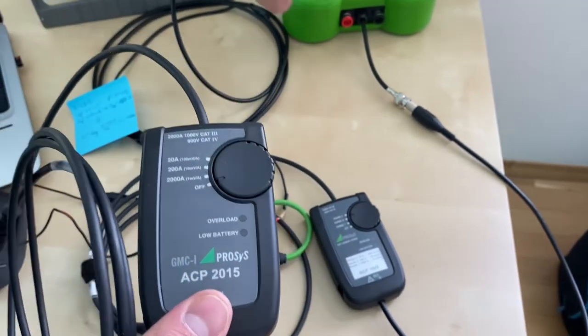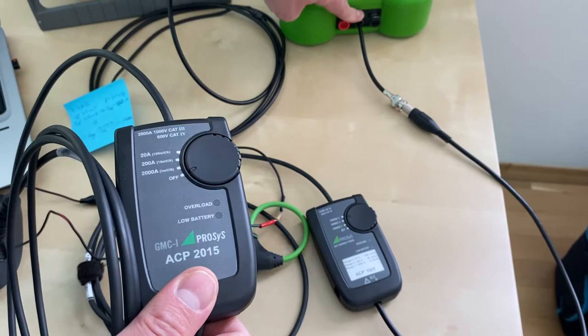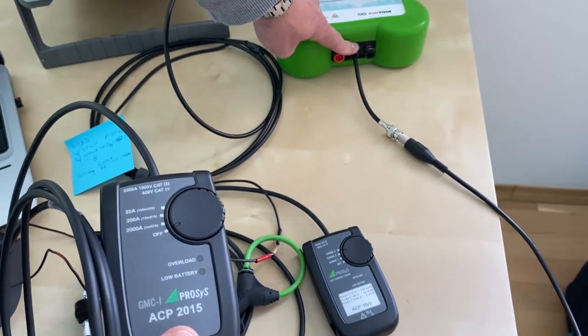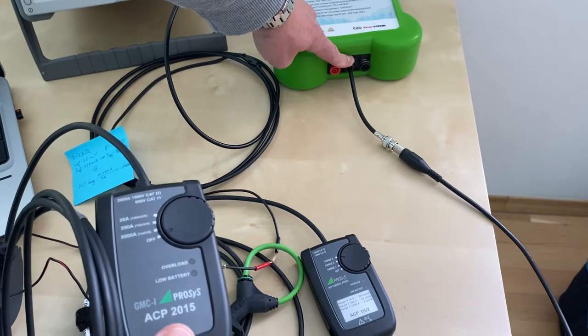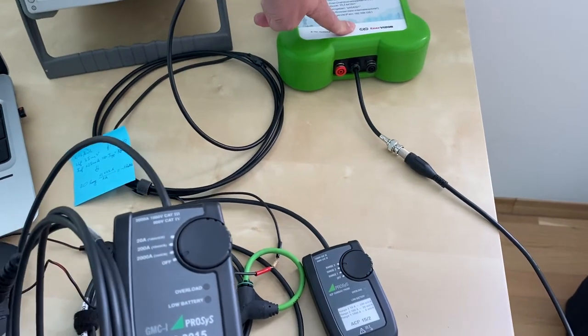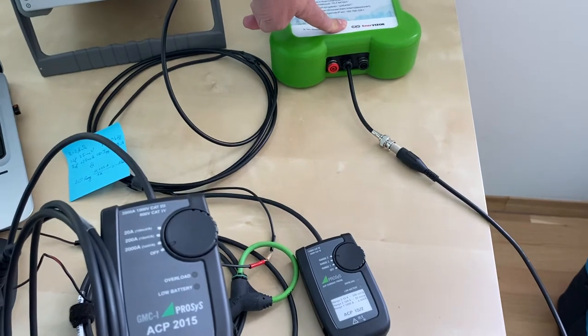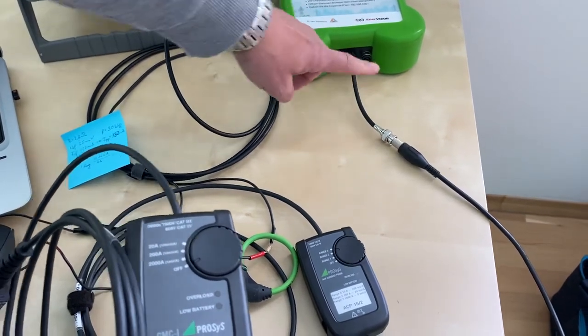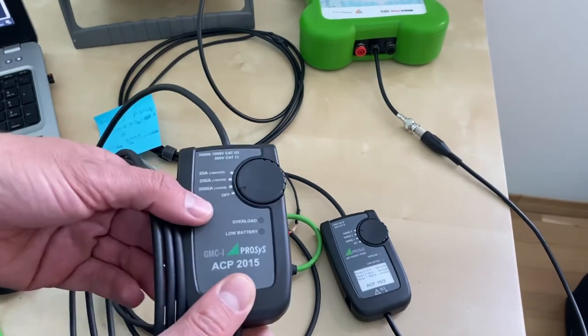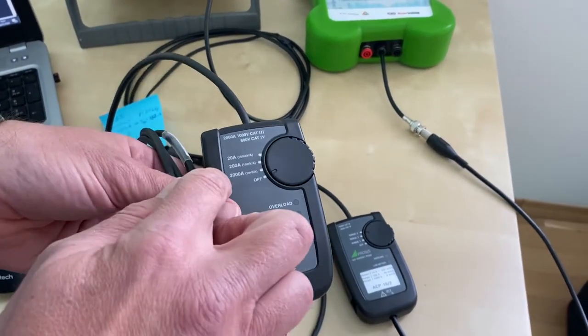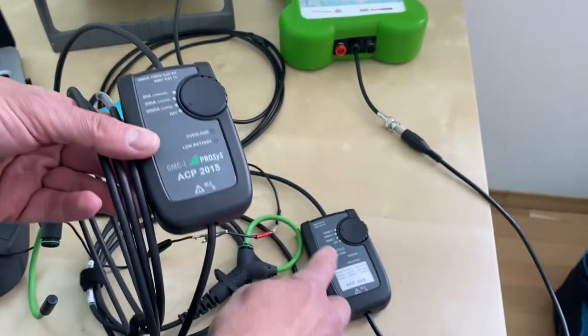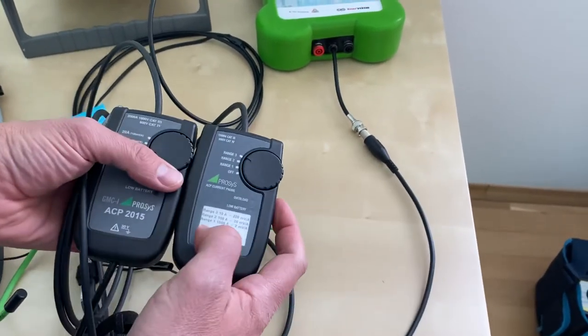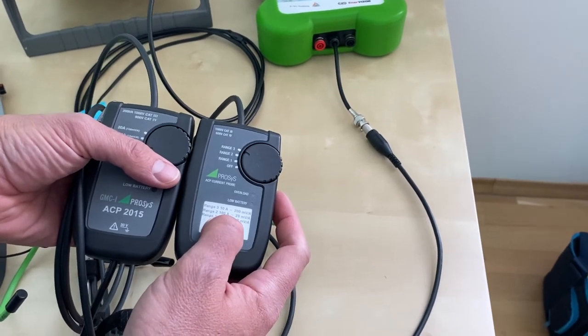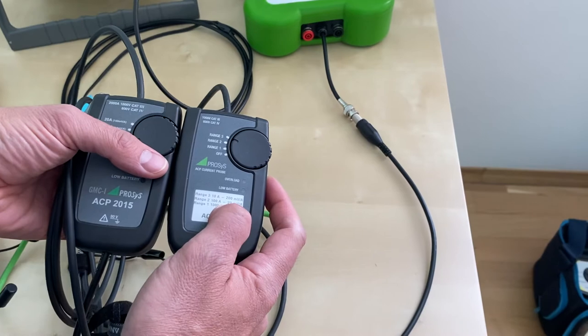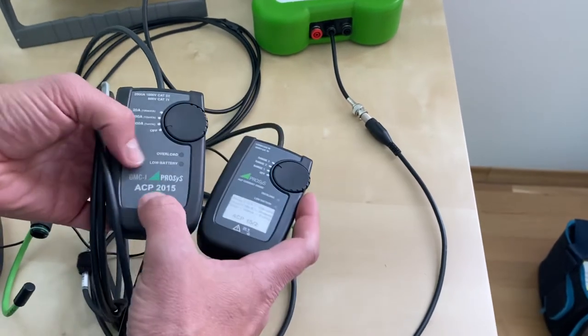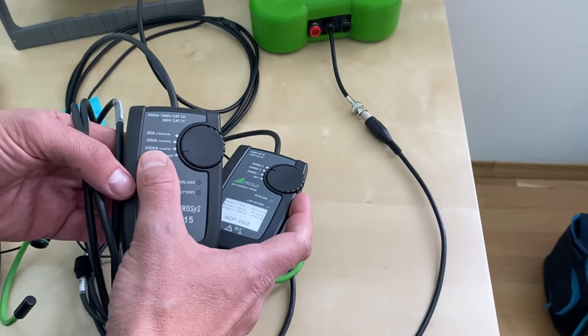Also note that in this input here, we have a maximum voltage we can cover, which is not 2 volts peak to peak, but 4 volts peak to peak, because inside there's an attenuation of 6 dB. So 4 volts peak to peak. The ranges can all be covered. Here the range is 200 amps, 2000 amps, and over here the range is 1000 amps. So 1000 amps in this case would mean 2 volts, and over here, 2000 would mean 2 volts just as well.